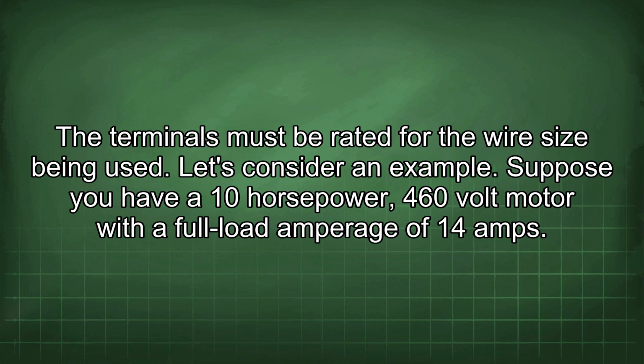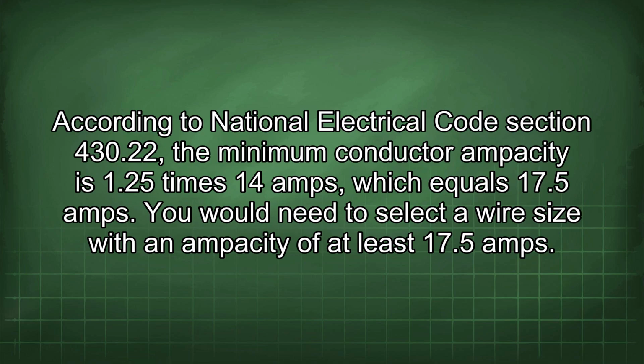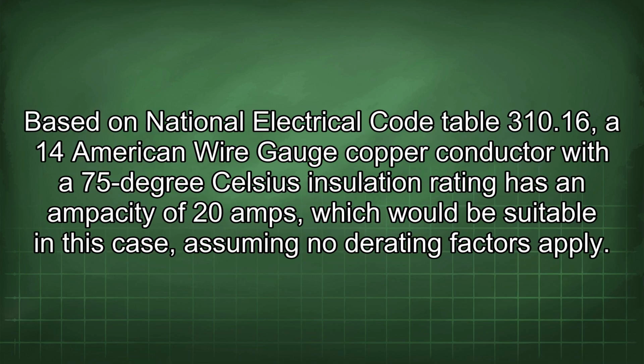Let's consider an example. Suppose you have a 10 horsepower 460 volt motor with a full load amperage of 14 amps. According to National Electrical Code Section 430.22, the minimum conductor ampacity is 1.25 times 14 amps, which equals 17.5 amps. You would need to select a wire size with an ampacity of at least 17.5 amps. Based on National Electrical Code Table 310.16, a 14 American wire gauge copper conductor with a 75 degrees Celsius insulation rating has an ampacity of 20 amps, which would be suitable in this case, assuming no derating factors apply.